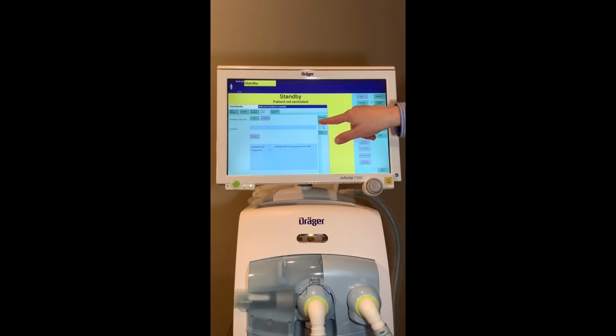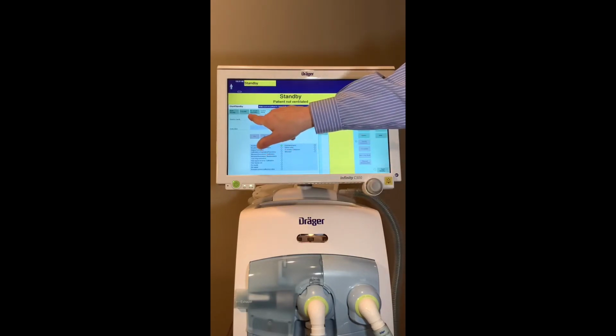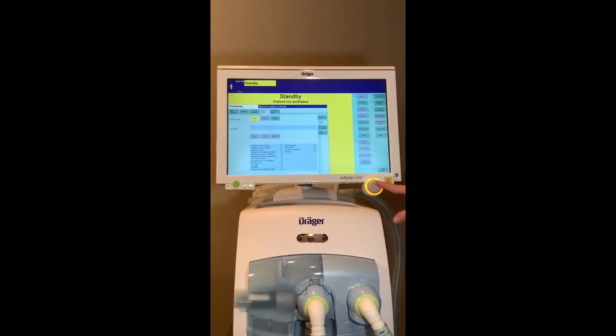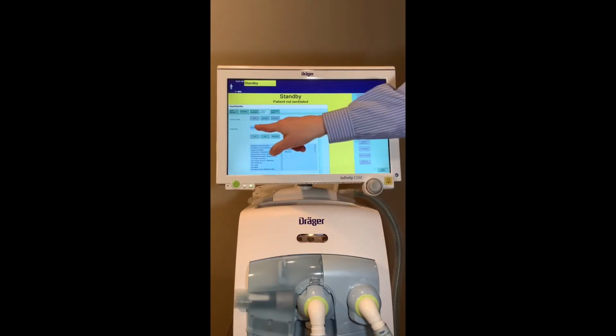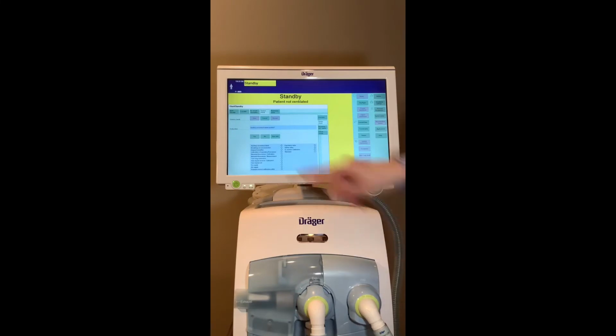To perform the device check, touch the device check button. The user chooses the start button, which will turn yellow, again pressing the rotary knob to confirm, and the user will be prompted with instructions which they'll answer using the buttons saying yes or no. The ventilator will go through each of the different components, and as long as each component passes, the device check is successful.